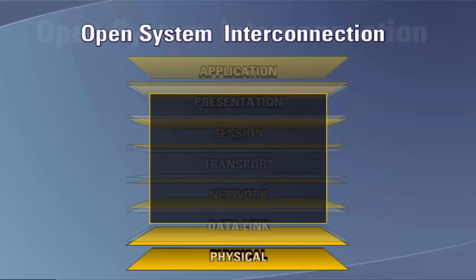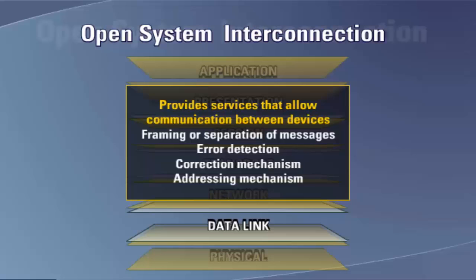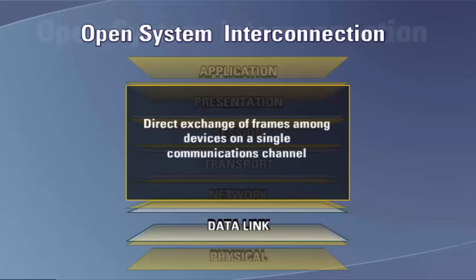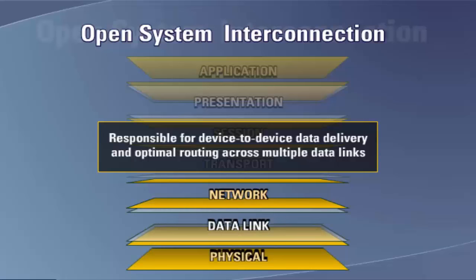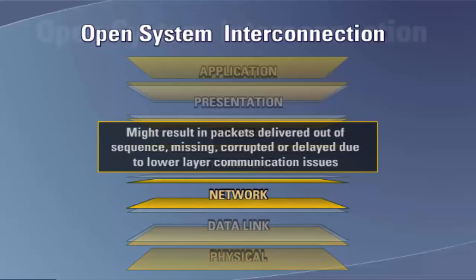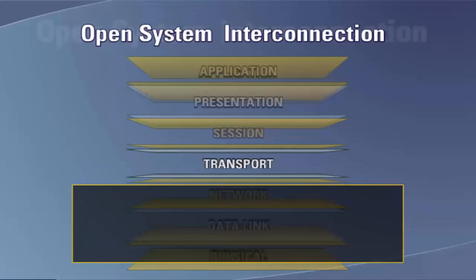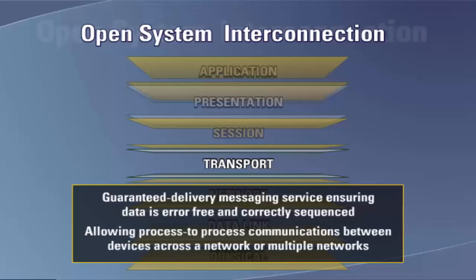In utility and industrial power system applications, the most commonly used physical layer standards are RS-232, RS-423, RS-485, 10/100 Base-T, and 10/100 Base-F Ethernet. The data link layer provides services for communication between devices, including framing, error detection and correction, and addressing. The network layer is responsible for device-to-device data delivery and optimal routing across multiple data links. The transport layer provides guaranteed delivery messaging service, ensuring data is error-free and correctly sequenced, allowing process-to-process communications across a network or multiple networks.